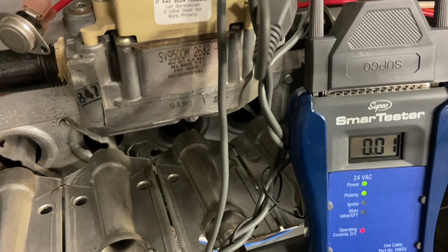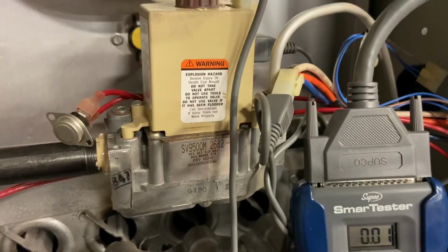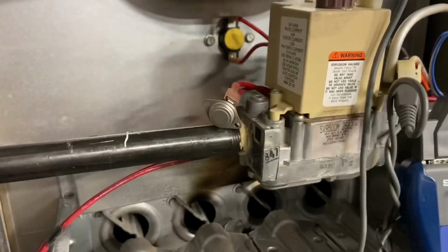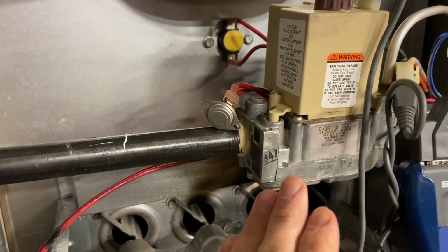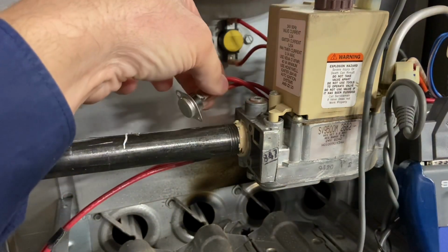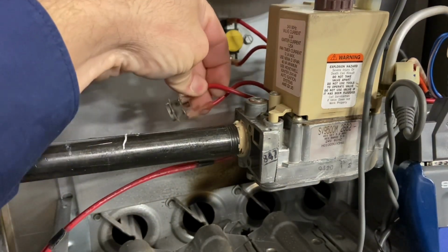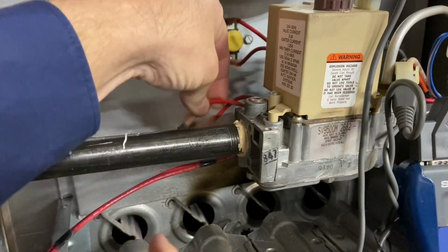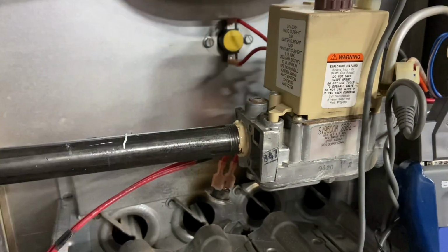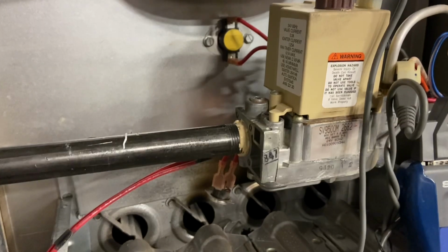So while we're on this, let's also point out a few other little things. This is our intermittent combination gas valve. Here is the limit switch. It's actually a flame rollout. This one is manual reset. It was on the plate that I took off so that we could get down here to the components so you can see the burners.